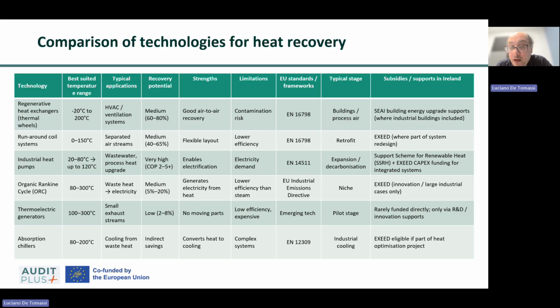Thermoelectric generators produce electricity directly from temperature differences using semiconductor materials. They can operate across a wide temperature range, but are generally most effective where large temperature gradients exist, typically above 100 Celsius degrees. Applications include remote monitoring systems, niche industrial recovery projects, and automotive waste heat recovery. Conversion efficiency is usually below 10%, making them less attractive for large-scale energy recovery.